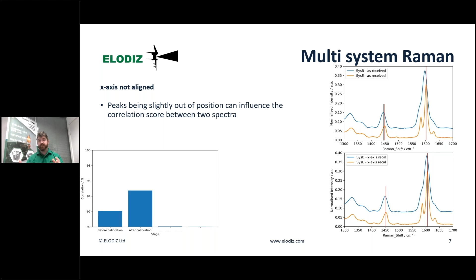What we can do if we just perform our recalibration is we have already reached that 95% threshold of saying that these two systems' spectra are matching in some way. However, you can definitely see that there is a difference that is based on the resolution between the two. As you can see, the blue line has a much lower resolution. All the peaks seem to be jumbled together, whereas the orange line, you can clearly distinguish different peaks.